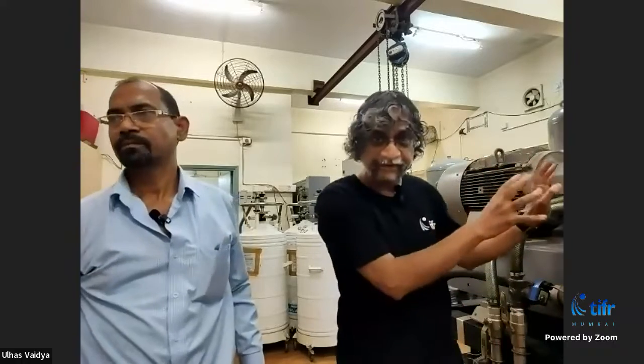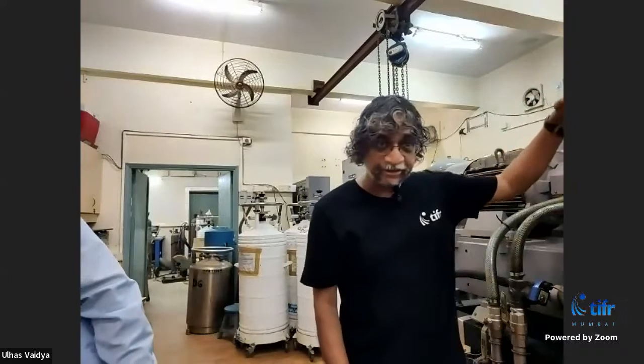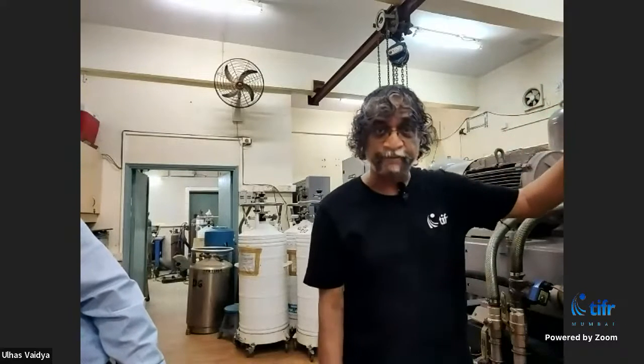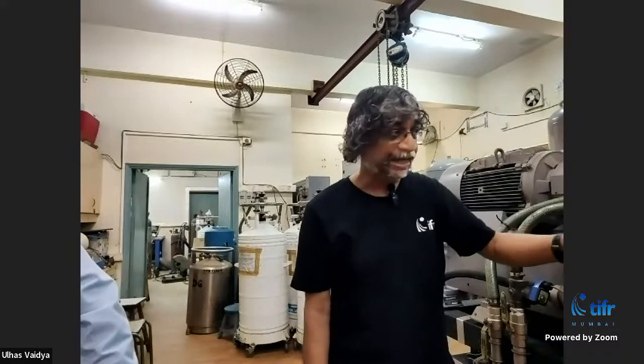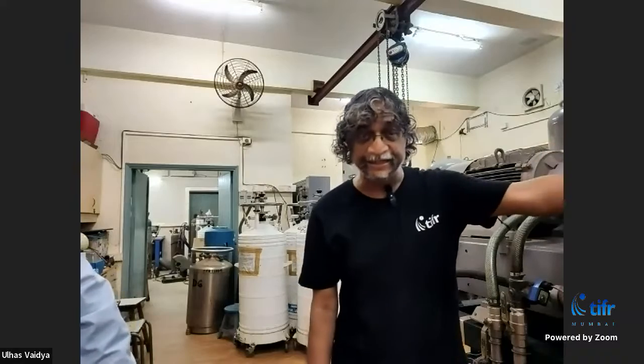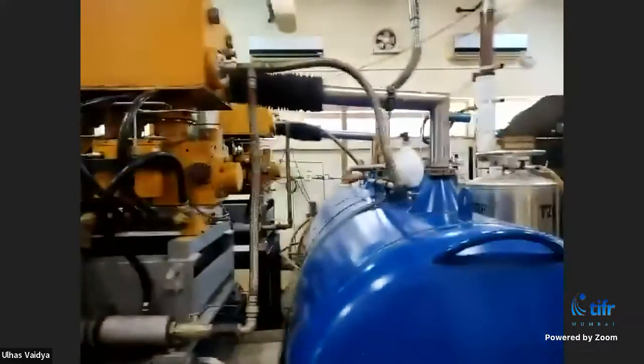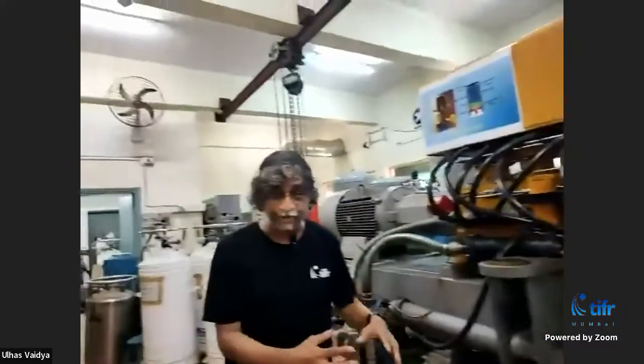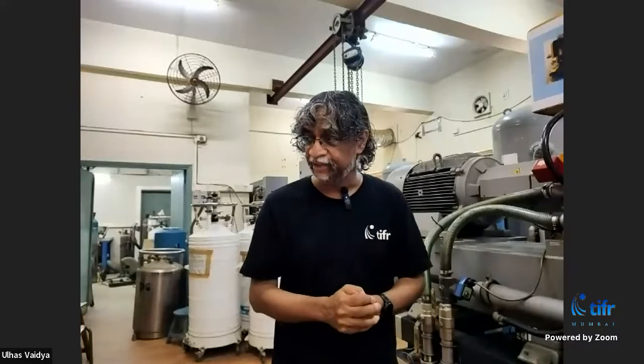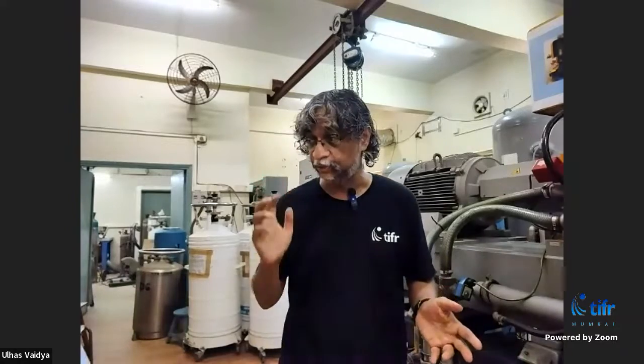But that's a fixed amount of helium in there. And then, because it reaches minus 200 on the top, the nitrogen that is flowing past it will get liquefied, and then it is collected in these big tanks that you see here. So when all 8 cylinders are working, this thing can produce up to about 100 liters of liquid nitrogen per hour. Okay. And liquid nitrogen is, of course, very useful for many experiments that we do in TIFR.